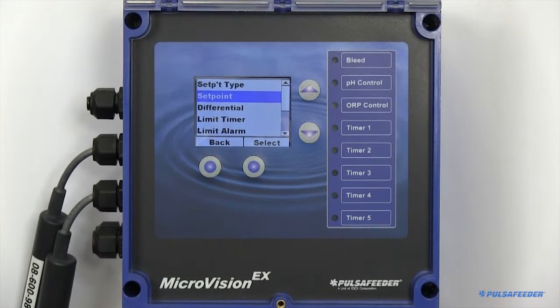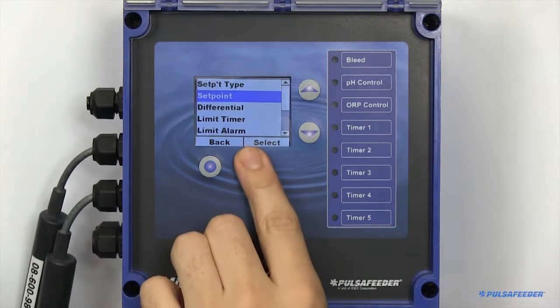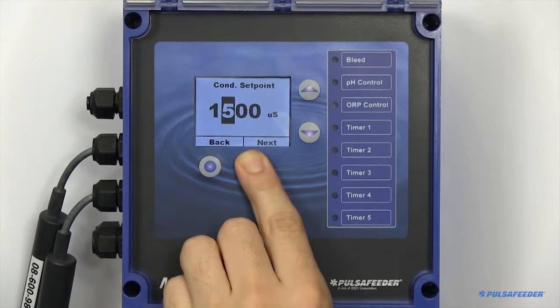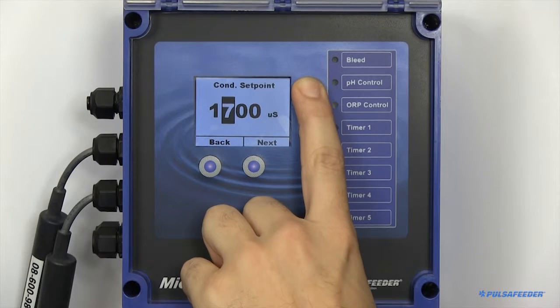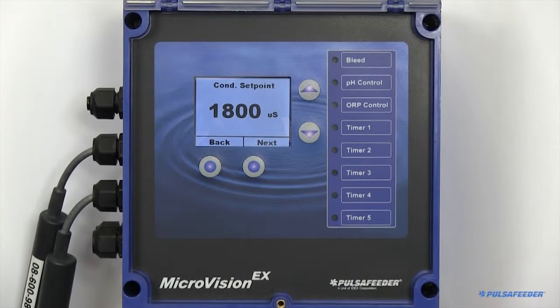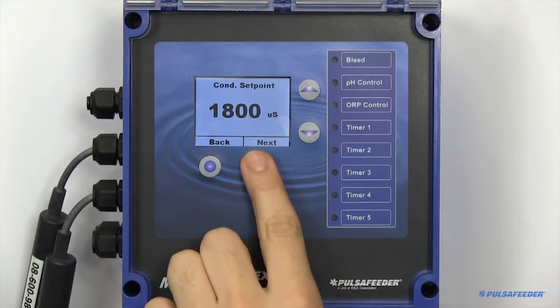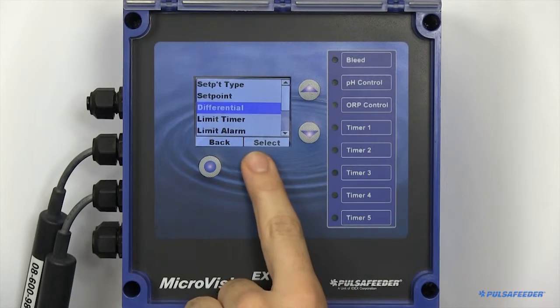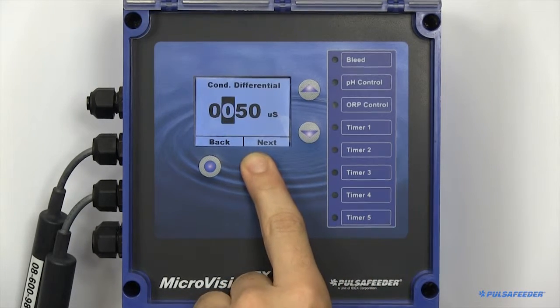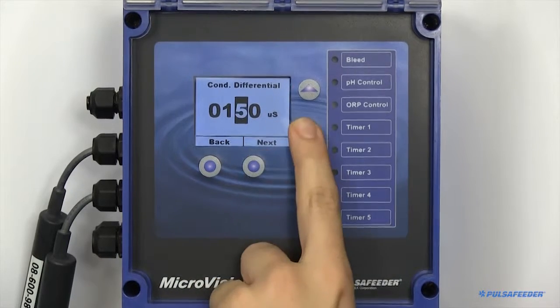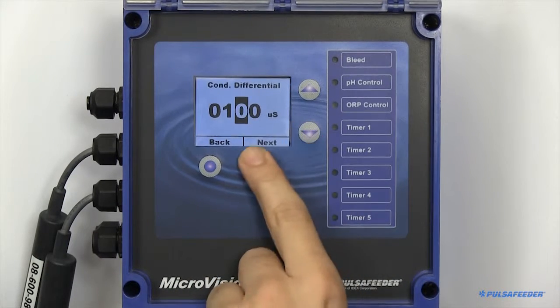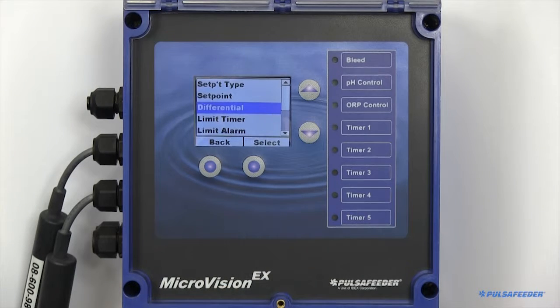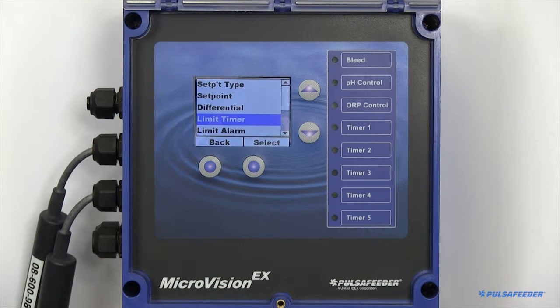Your set point is where the desired function will begin. The differential, or dead band, is the offset value which must be satisfied before the relay will turn off. Limit timers can also be enabled.